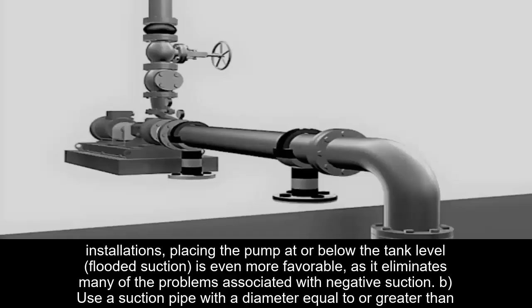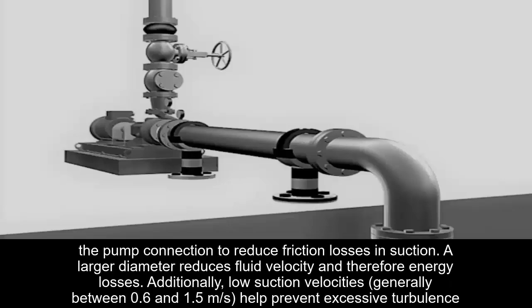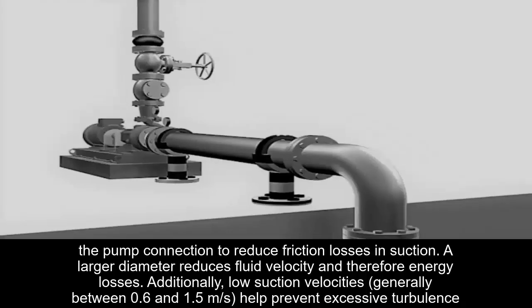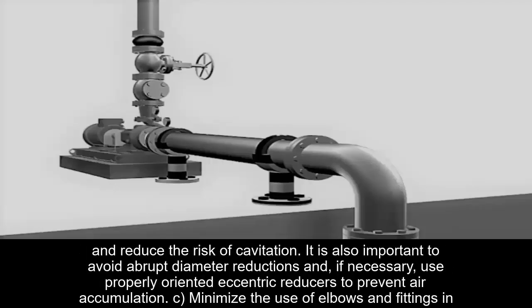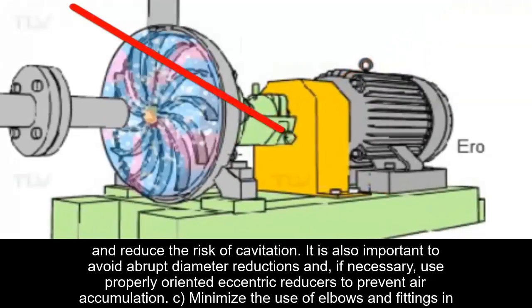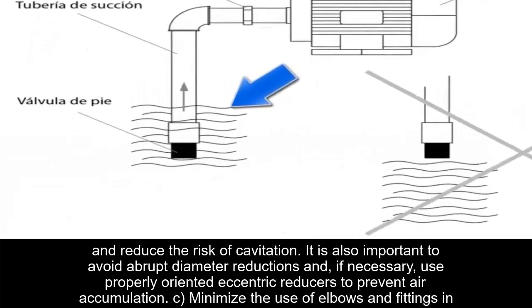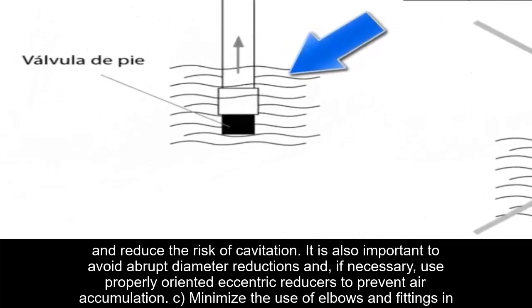B. Use a suction pipe with a diameter equal to or greater than the pump connection to reduce friction losses in suction. A larger diameter reduces fluid velocity and therefore energy losses. Additionally, low suction velocities, generally between 0.6 and 1.5 meters per second, help to prevent excessive turbulence and reduce the risk of cavitation. It is also important to avoid abrupt diameter reductions and, if necessary, use properly oriented eccentric reducers to prevent air accumulation.